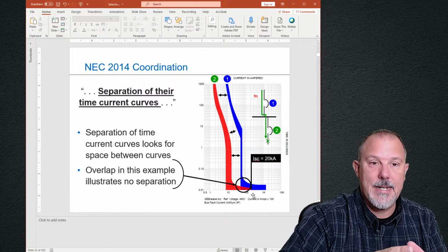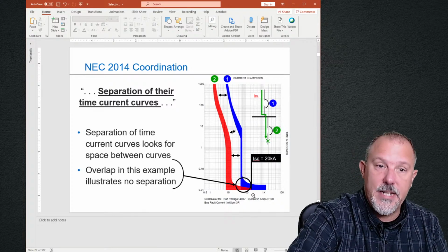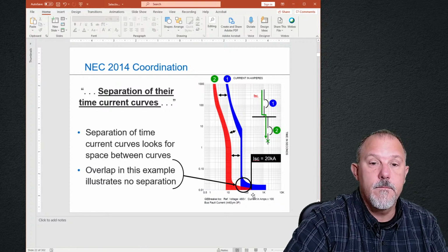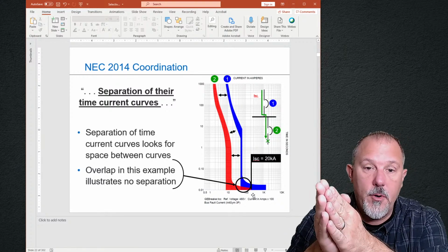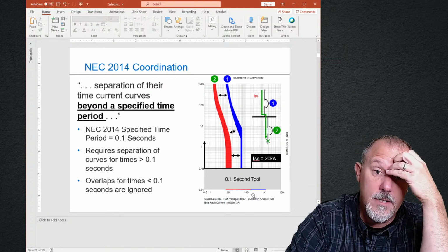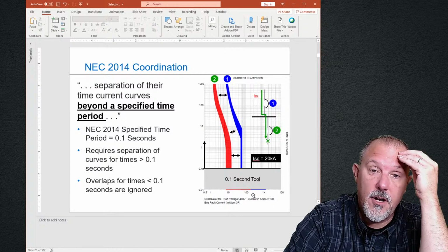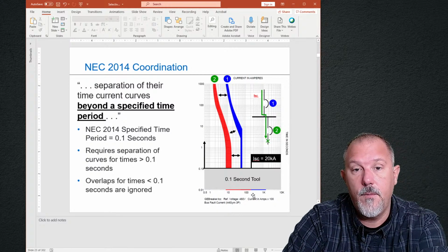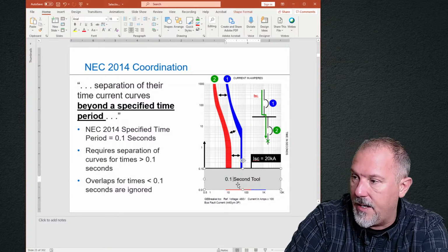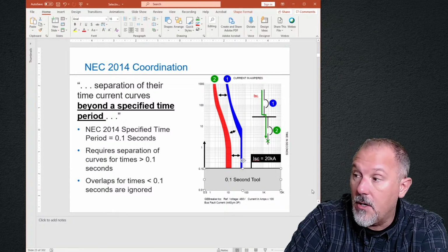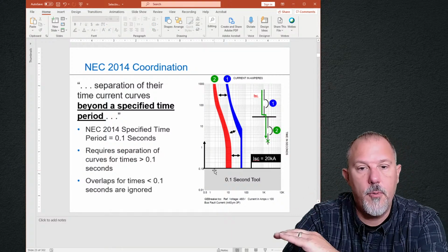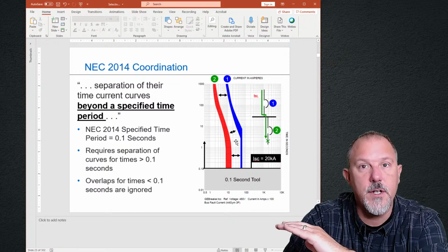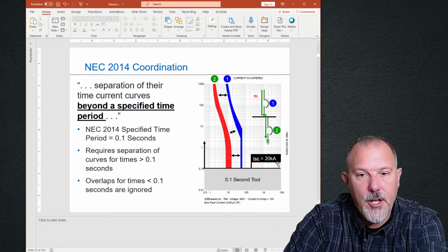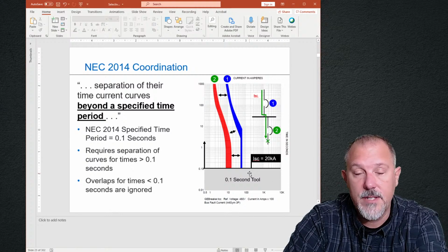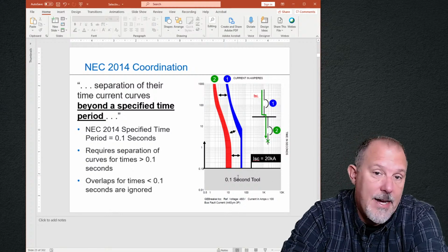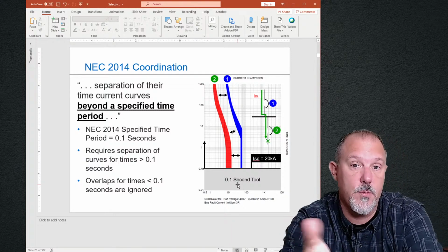So what 0.1 seconds does is it looks for separation of their time current characteristic curves. Now, I know that I have separation above 0.1 seconds, but below 0.1 seconds, I have this heel down here. But what we do in a healthcare environment, we cover up anything below 0.1 seconds. You don't want to see it. In fact, my little ruler here is not good. I got to get rid of it all. So I cover everything below 0.1 seconds, and I make sure I have separation of curves above 0.1 seconds. But then, as engineers, we know for 20,000 amps, even if I hide everything below 0.1 seconds, I know for a fact those will still open.